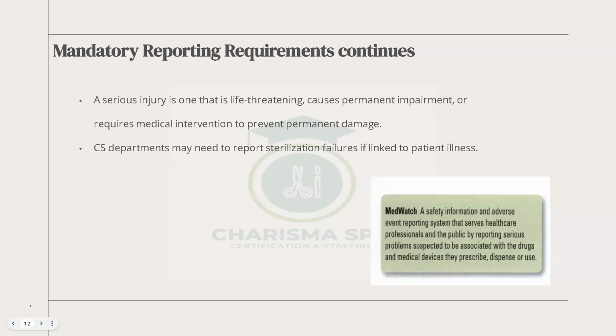I remember there was a time we had a pack of indicators, which is also a class 2 medical device. These indicators were not passing. It means that the chemical was not traveling to the safe zone for us to declare the instrument as being sterilized. So we needed to report to the manufacturer that there was something not right. As CSPD, we also need to report sterilization failures if we receive them, so that those items will not be used on patients, who at the end of the day will come back with more complications.